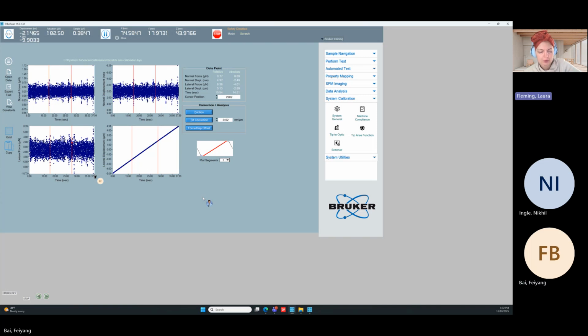Okay. So this scratch axis calibration needs to be done every day that you intend to do scratch. It should also only be performed after the indentation axis calibration, since we are also using the normal force to calibrate too. Does that make sense? Any questions on the calibration part?